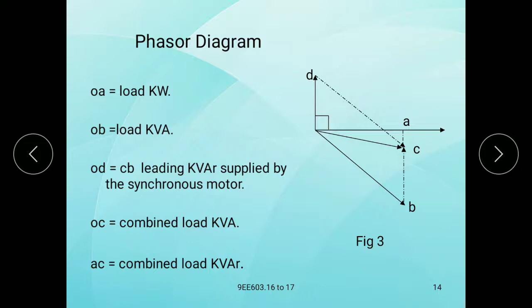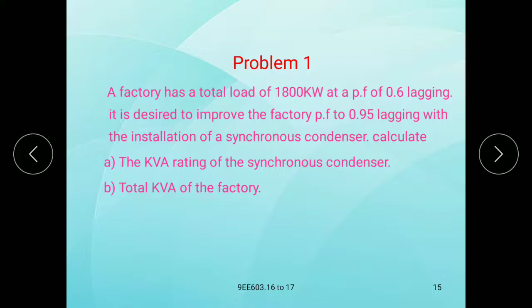Now, problems. Here, a factory has a total load of 1800 kilowatts at a power factor of 0.6 lagging. It is desired to improve the power factor to 0.95 lagging with the installation of a synchronous condenser. Calculate the KVA rating of the synchronous condenser, and the total KVA of the factory. Here, observe this one.